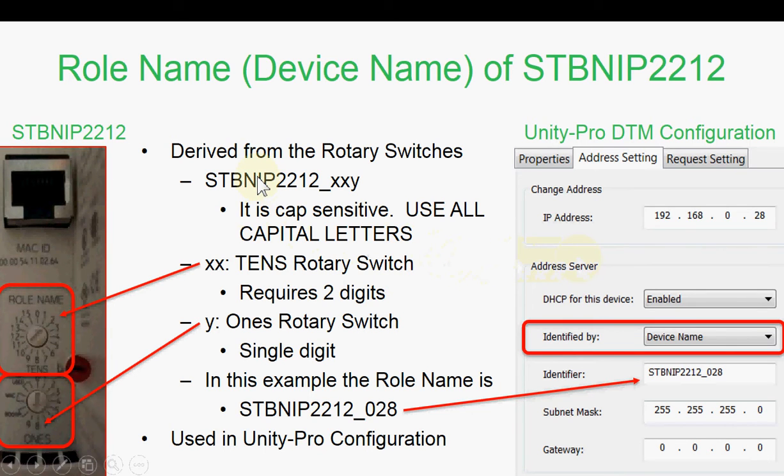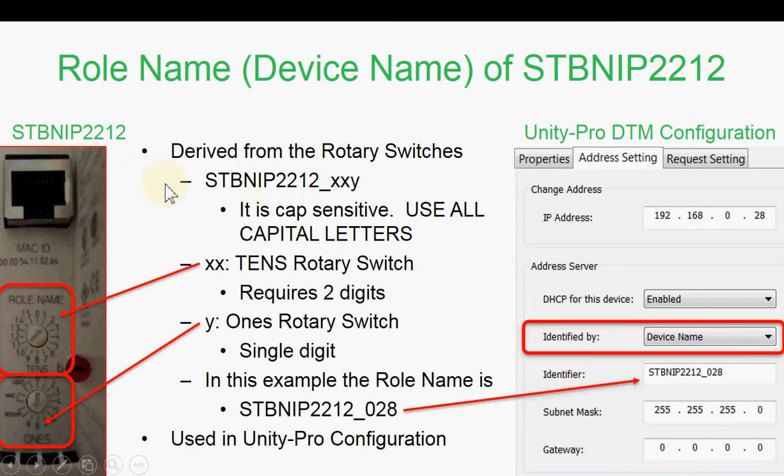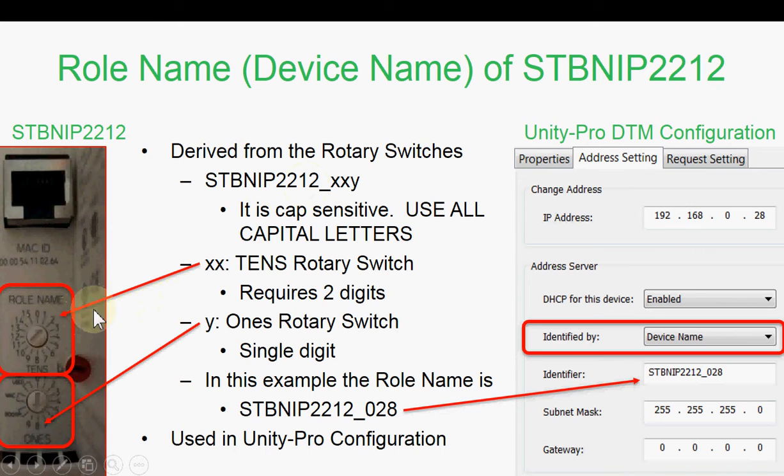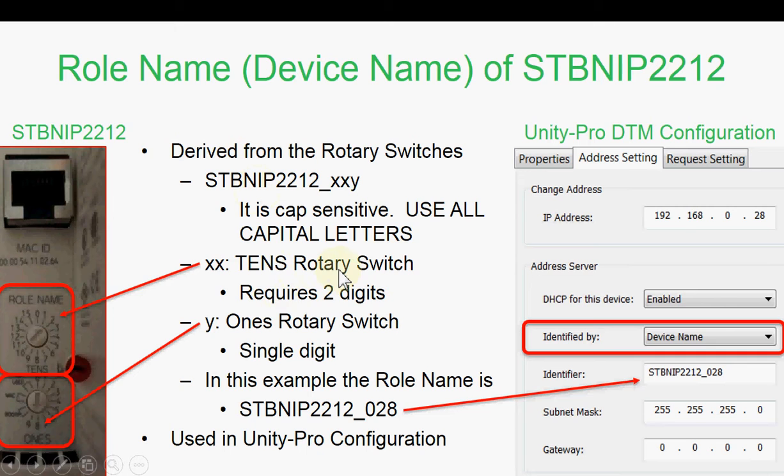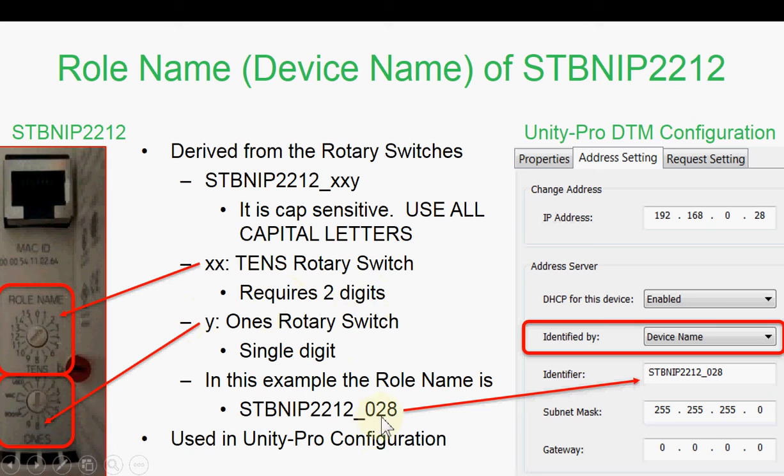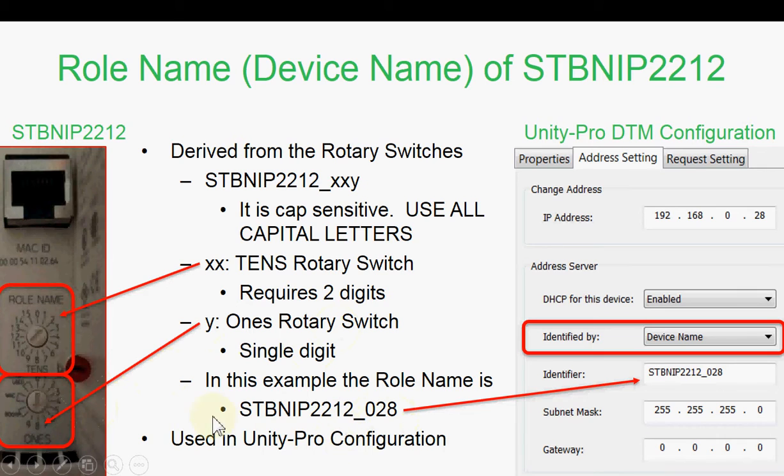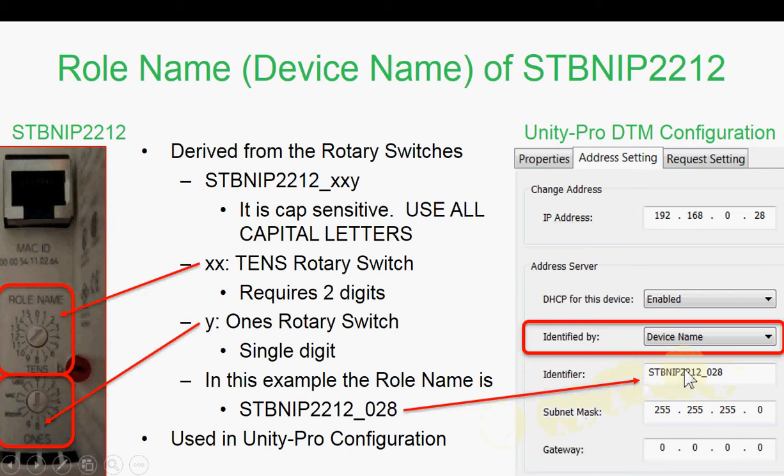Our Advantys STB has a default name based on the part number and the rotary switches. The part number is all caps. The 10s rotary switch in our case is set to 2, but it's two digits, so you're going to see 0, 2. The 1s is set to 8. So we have 0, 2, 8. And this name matches exactly the name in the identifier. You'll see that when we configure it in Unity Pro.